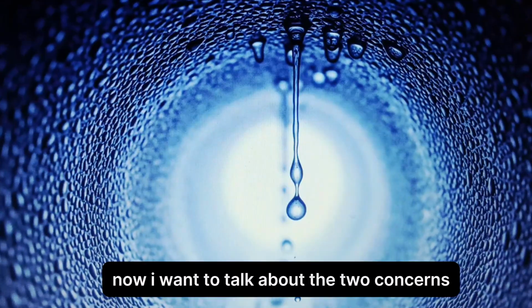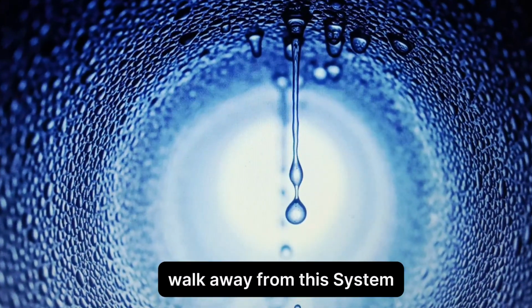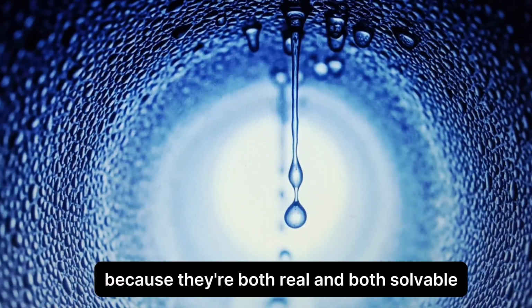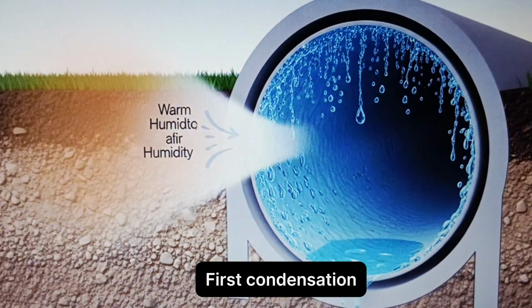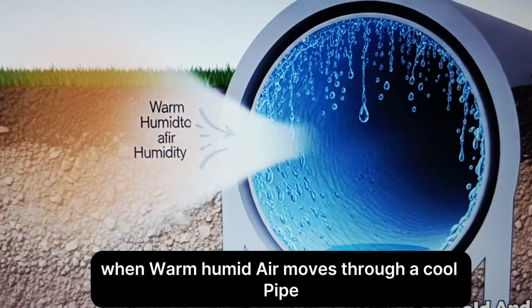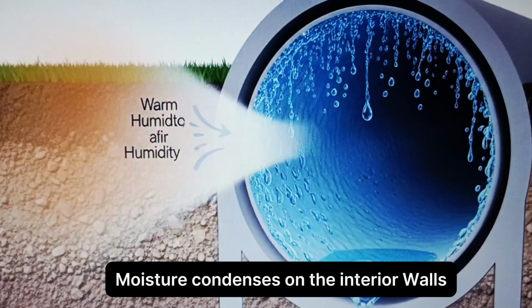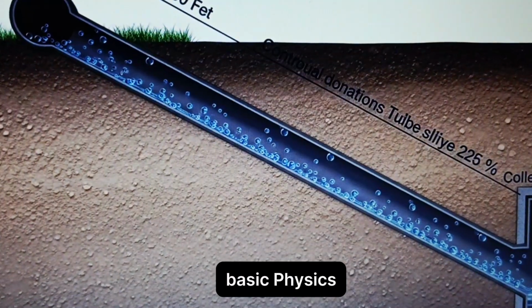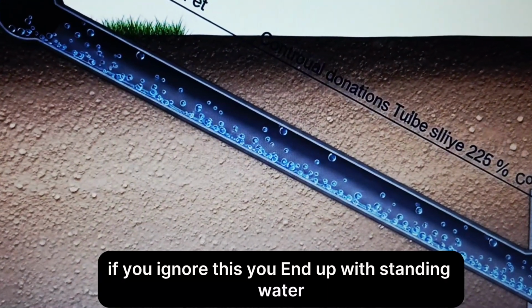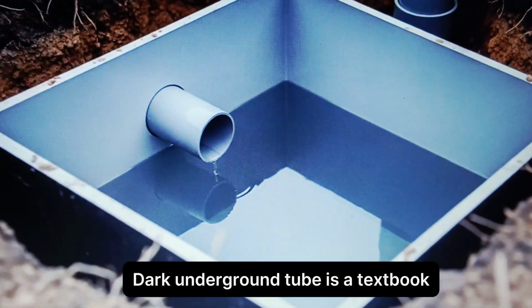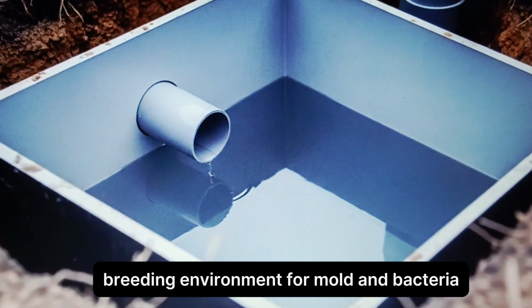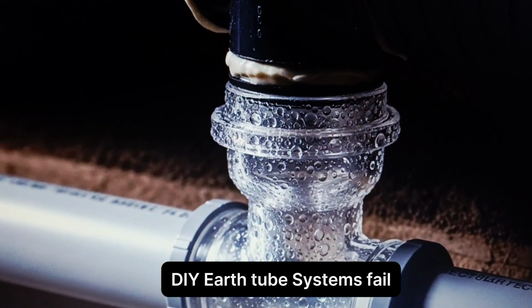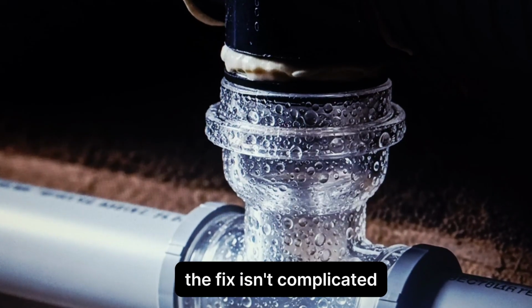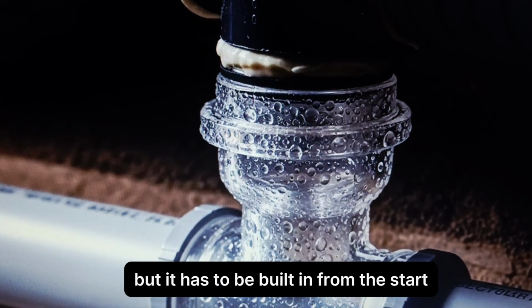Now I want to talk about the two concerns that make people walk away from this system, because they're both real and both solvable. First, condensation. When warm, humid air moves through a cool pipe, moisture condenses on the interior walls. Basic physics. If you ignore this, you end up with standing water inside your pipes. And standing water in a warm, dark underground tube is a textbook breeding environment for mold and bacteria. This is the number one reason DIY earth tube systems fail. The fix isn't complicated, but it has to be built in from the start.